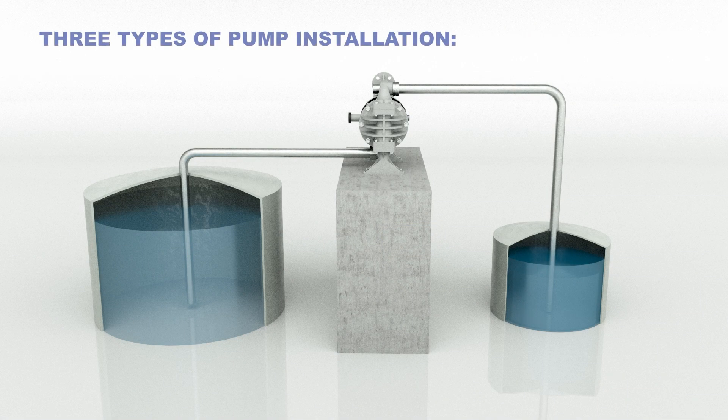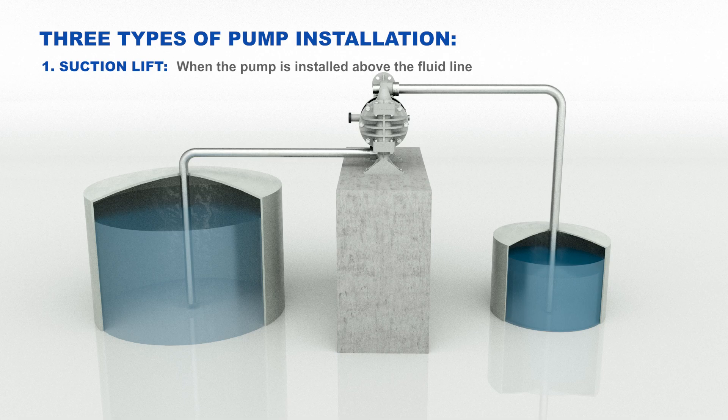Three types of pump installation include suction lift. When the pump is installed above the fluid line, ensure that the suction dry lift capability of the pump exceeds the height difference. Note, be sure to take the specific gravity of fluid into account.